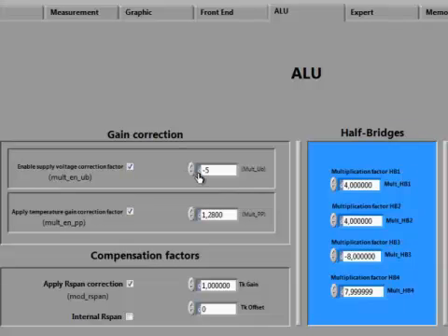You can enable the gain compensation for the temperature behavior of the electronics by setting this bit here. The correction factor itself can be set here. The factors that are used for correction of the gain and offset drift of the whole system over temperature, namely the Tk gain and Tk offset, are to be set here. The enable bit to enable the temperature compensation and correction is the mod R-span bit here. If the temperature compensation is to be performed with the integrated R-span resistor in PS09, that is RTEM, then the internal R-span bit is to be set.